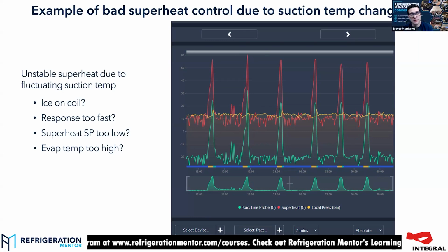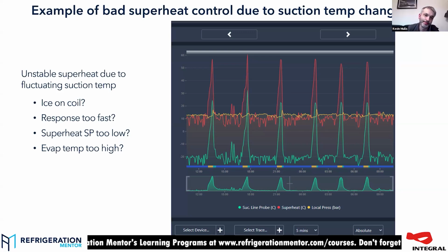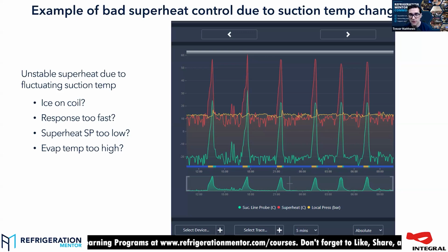Yeah, and that's the thing. Especially in CO₂ systems, you've got so many electronic valves, you need them all to be working in sync. The high pressure valve, the flash gas bypass valve, and the case valves, because if some of the case valves are out, that's going to affect all the other valves and the way the rack turns on and off, just like you're saying. So, I like the point you made about the superheat being set too low. I've seen this time and time again doing electronics trainings, where the valve's opening and closing and opening and closing. It's the same with a TX valve. If you set it too low, the valve is going to open and close.